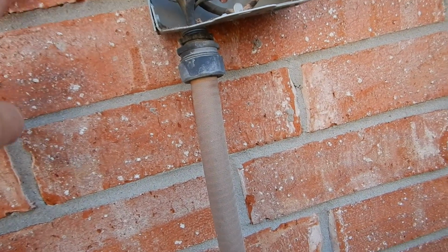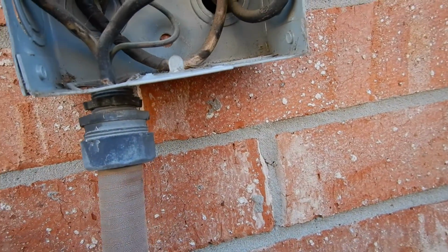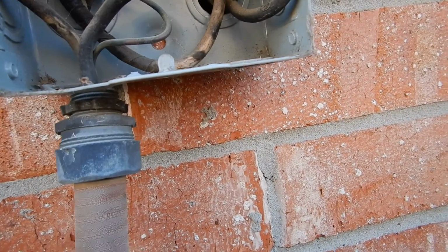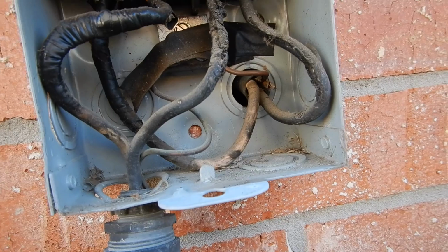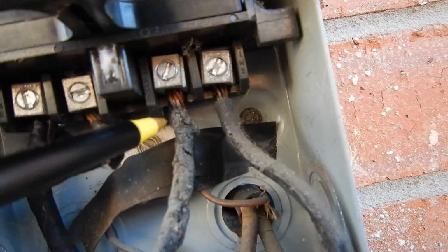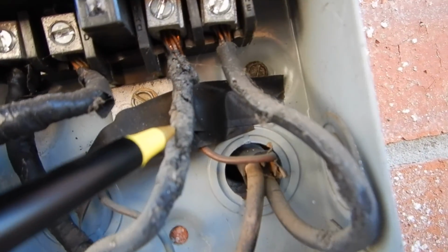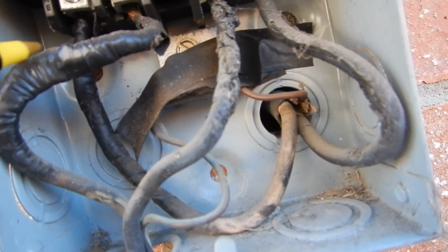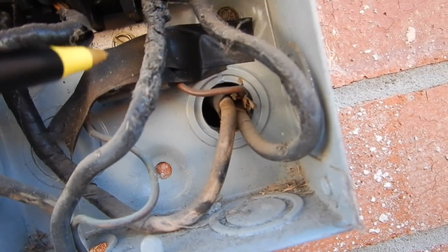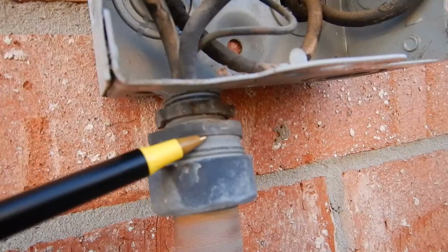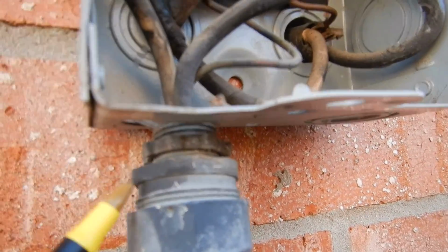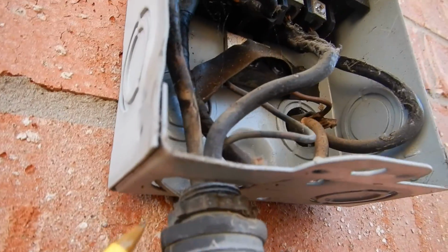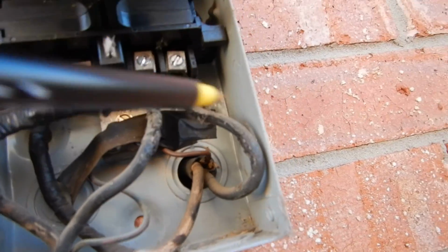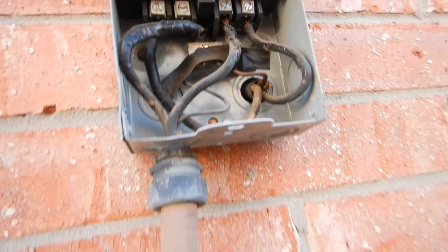Now, we've got something very interesting going on here, and this is why I like to take these guys off. We've had a heat event. See the scorching in there, and see all this coming off, and then somebody's taped this up to make repairs, and then the electric conduit is loose. It's loose from the box. That should have been sealed up better. This wiring should be replaced.